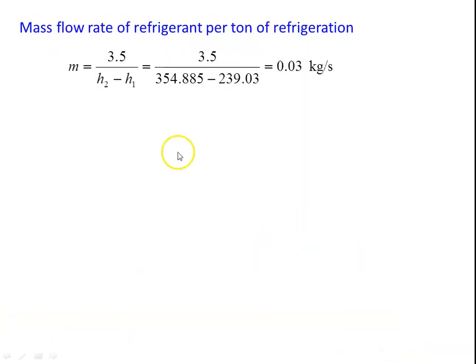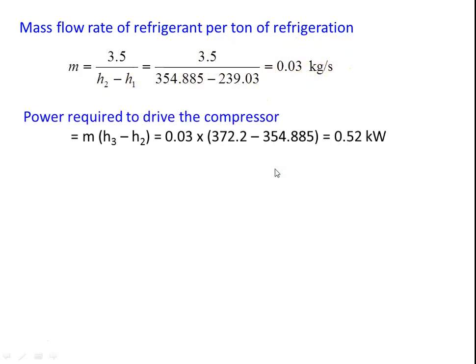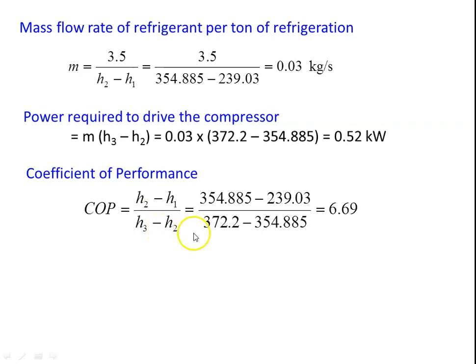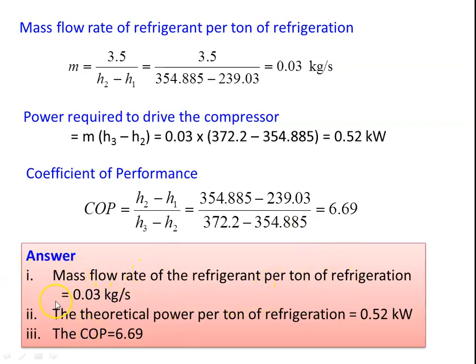Mass flow rate per ton of refrigeration: 1 ton of refrigeration equals 3.5 kJ/s. So mass equals 3.5 divided by (H2 minus H1), giving 0.03 kg/s. Power required to drive compressor: M into (H3 minus H2) equals 0.03 into (372.2 minus 354.885) equals 0.52 kilowatts. COP equals (H2 minus H1) divided by (H3 minus H2), substituting all values gives 6.69. Answers: mass flow rate per ton of refrigeration is 0.03 kg/s; theoretical power per ton of refrigeration is 0.52 kilowatts; COP equals 6.69.